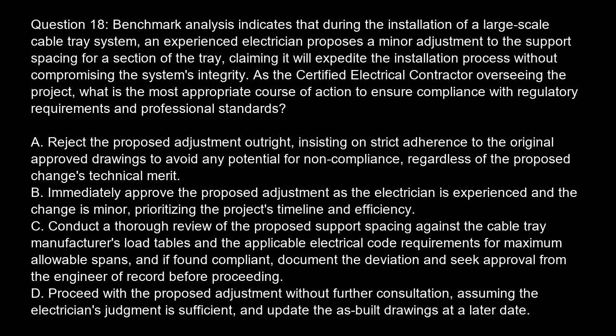Option C. Conduct a thorough review of the proposed support spacing against the cable tray manufacturer's load tables and the applicable electrical code requirements for maximum allowable spans, and if found compliant, document the deviation and seek approval from the engineer of record before proceeding. Option D. Proceed with the proposed adjustment without further consultation, assuming the electrician's judgment is sufficient, and update the as-built drawings at a later date.